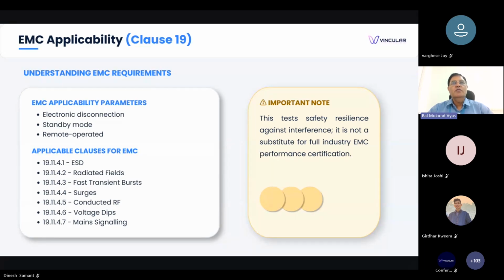IS 302-1 includes evaluation of electronic controls under EMC stress conditions, and the tests described in this clause are electrostatic discharge, electromagnetic high-frequency field immunity, electrical fast transients, high-energy surges, conducted RF susceptibility, voltage dips and interruptions, immunity to harmonics and interharmonics. For example, with electrostatic discharge application, the safety function should remain operational, unsafe outputs should not be activated, and appliances should recover safely. So this is very important, and this is similar for all the tests. So this EMI/EMC testing covers immunity requirements. It does not cover the emission requirement in IS 302-1.